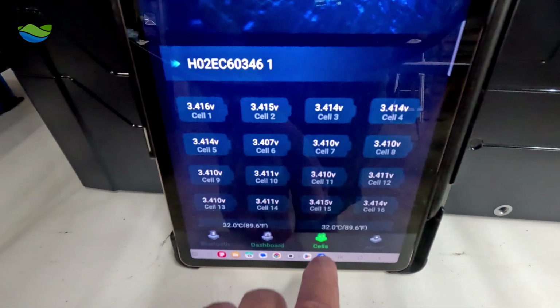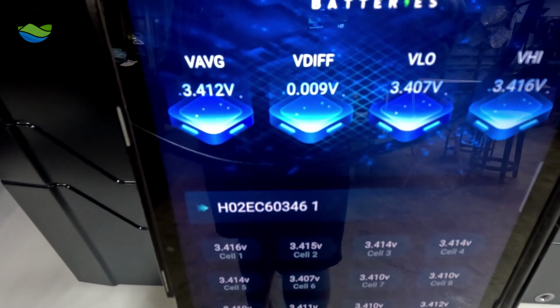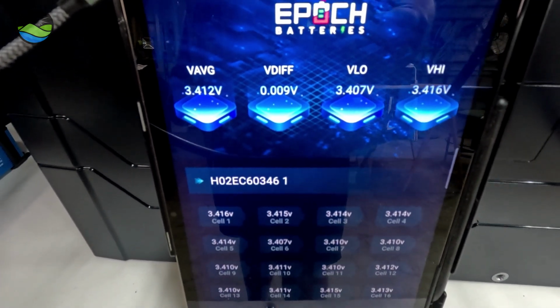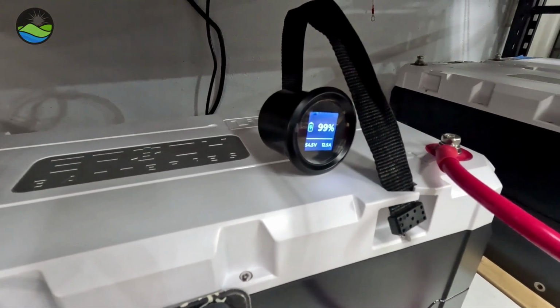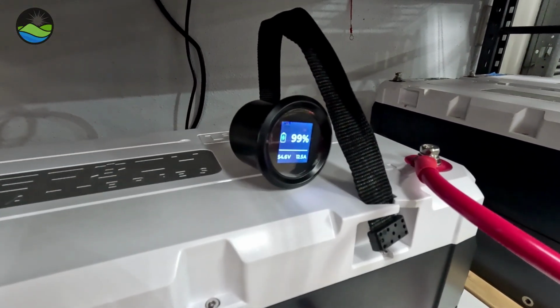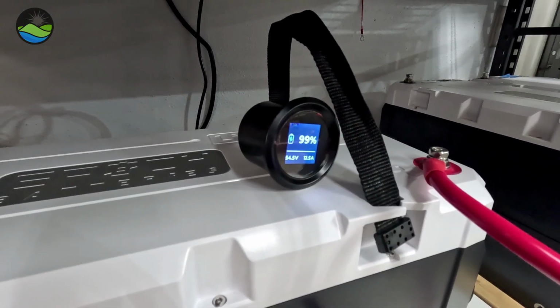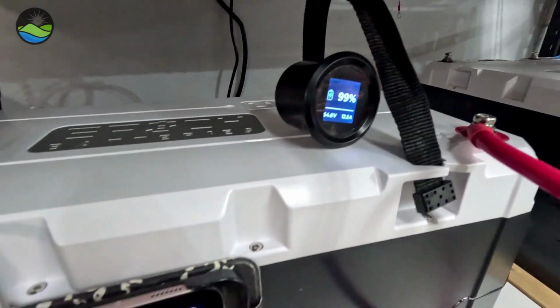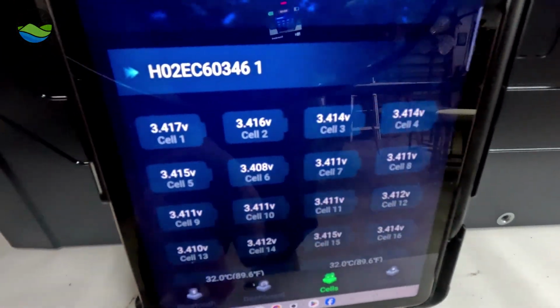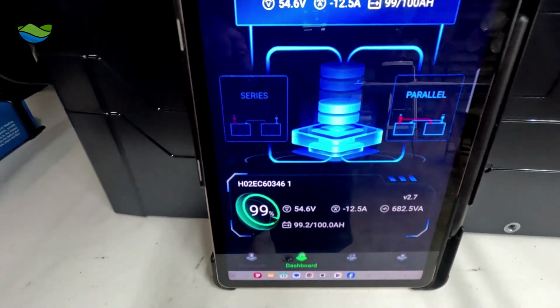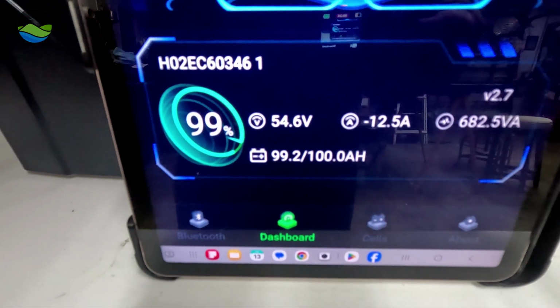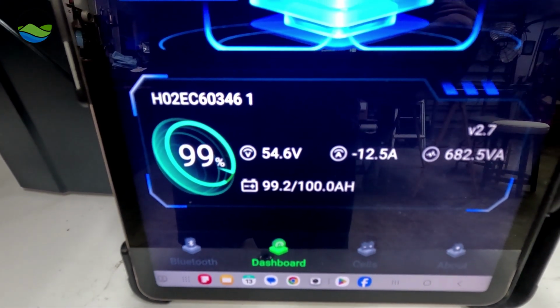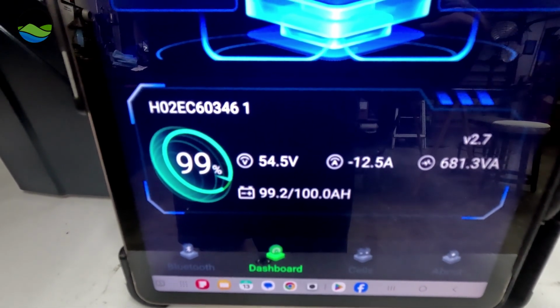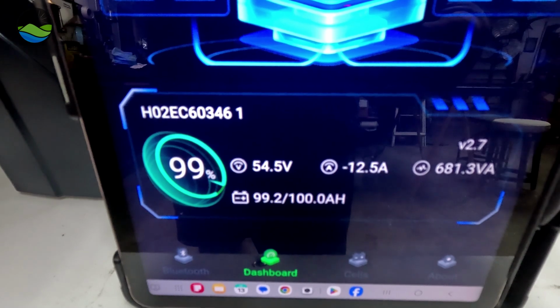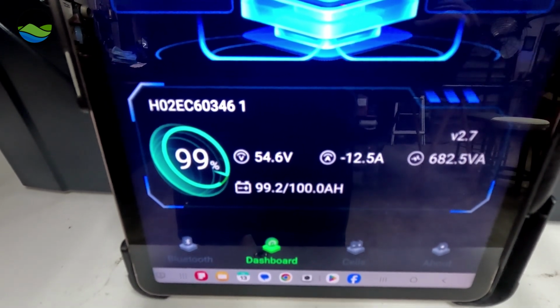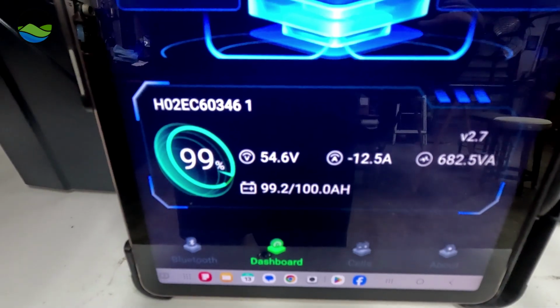If we go to the cells tab, we're at a 0.009 volt differential. Now it shows 99%, so we're getting close there. SOC is moderately accurate, so never count on SOC to be perfectly accurate. But from here, the voltage will begin to rise very quickly. 54.6. You'll see it spend a lot of time during the charge at a mid-level voltage, but once it gets up into the upper knee, you'll see that voltage start to climb very rapidly.